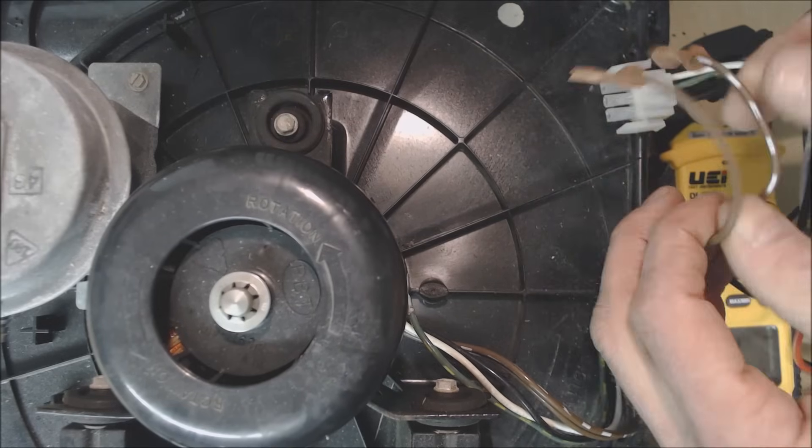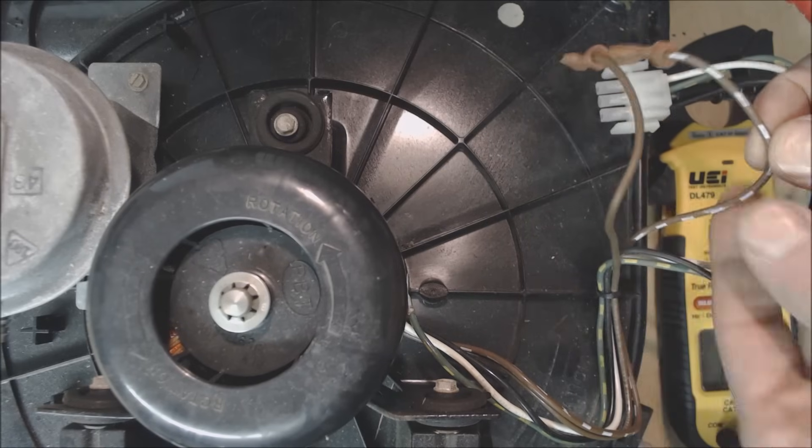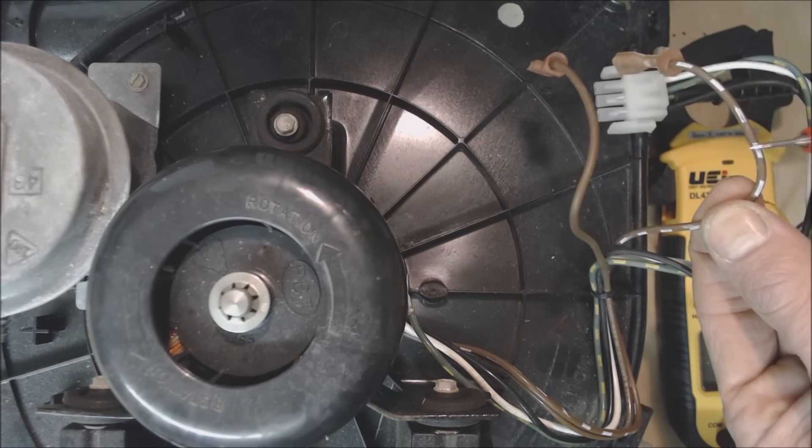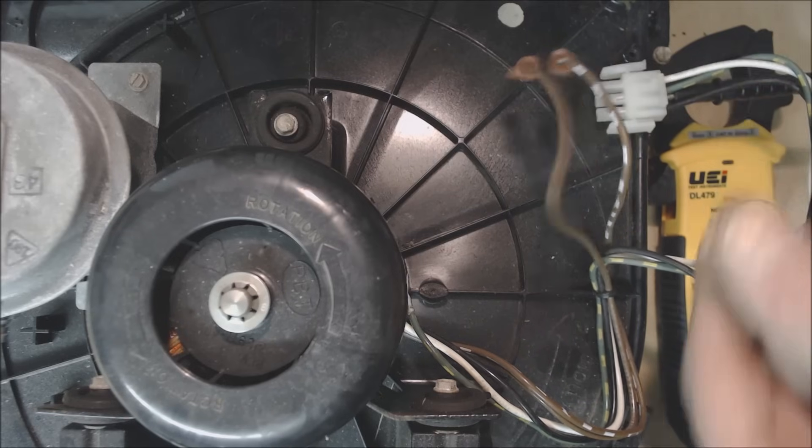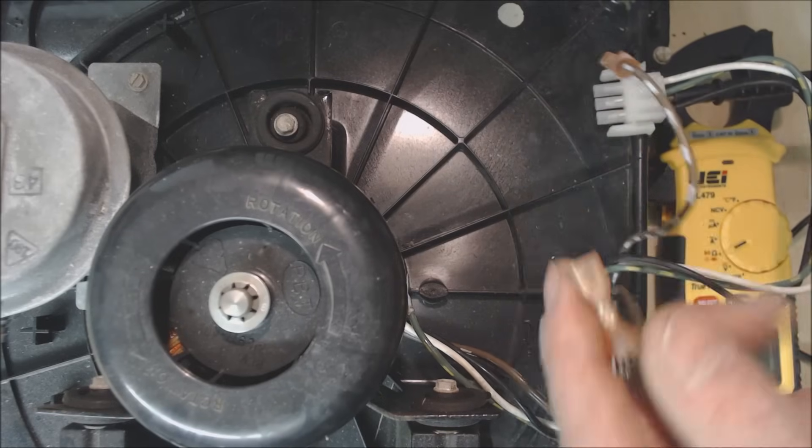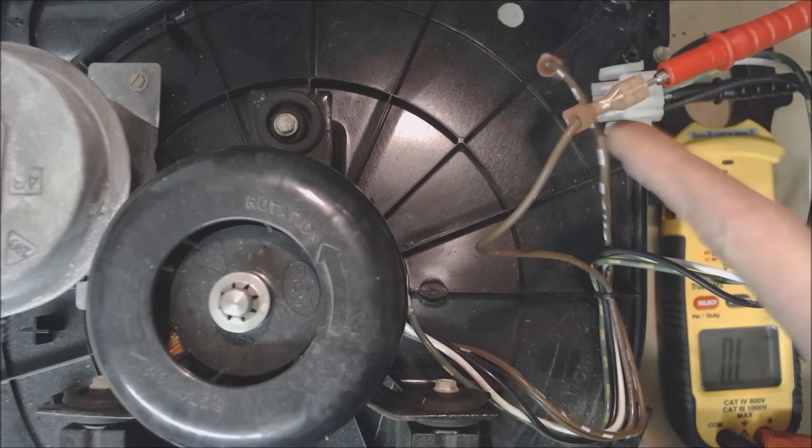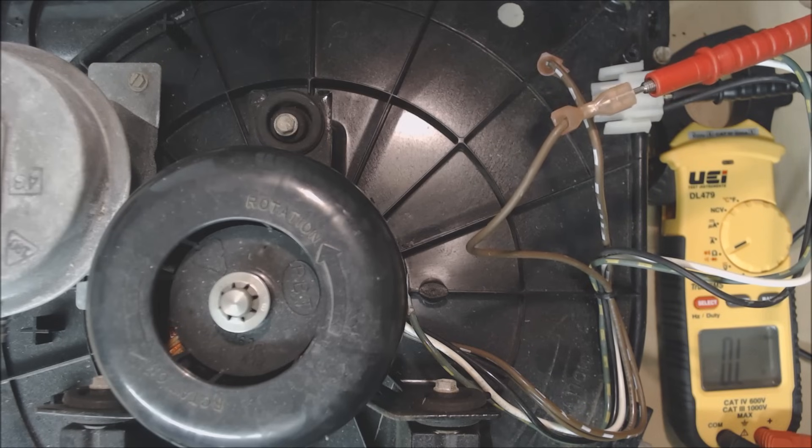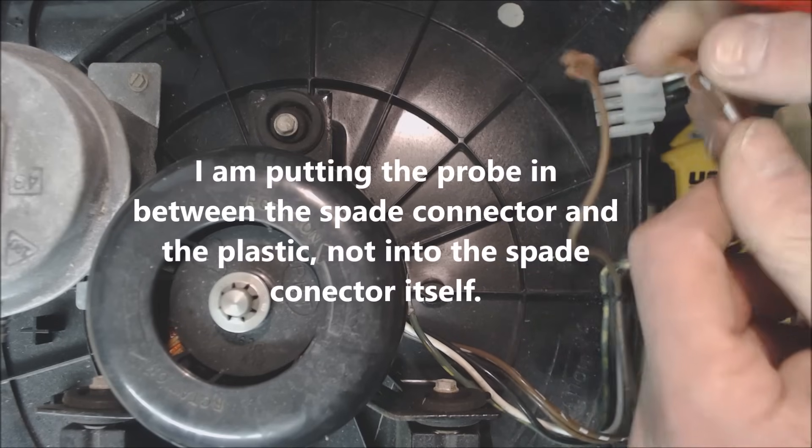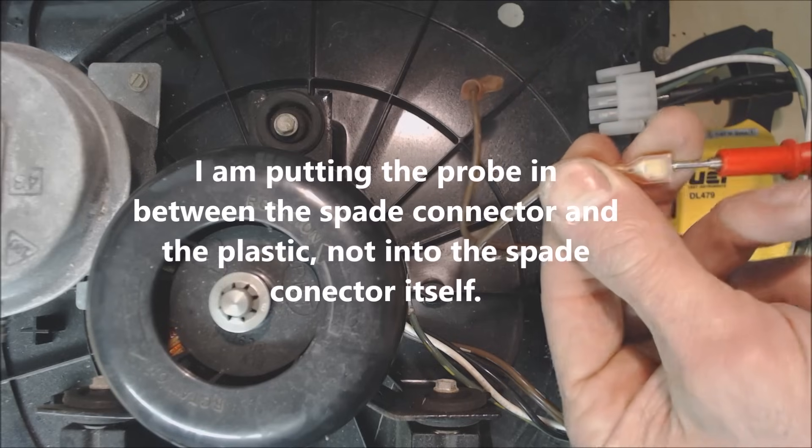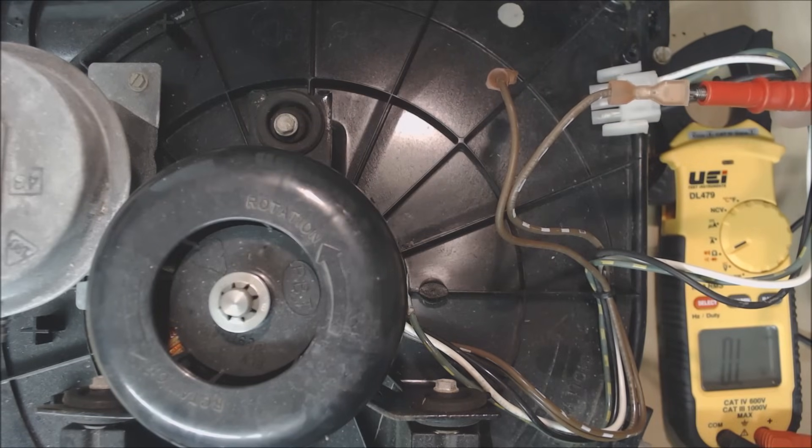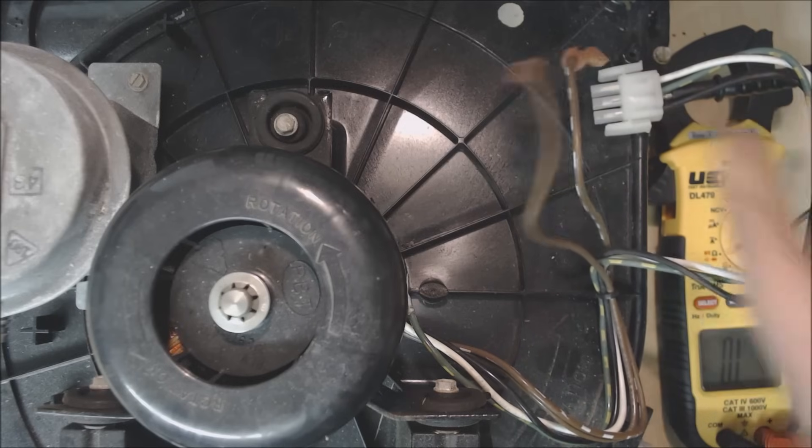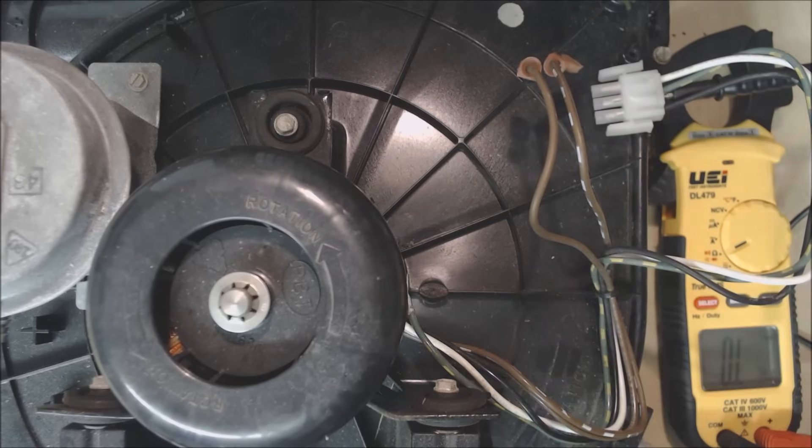And just so you know, when you have the two wires going to the capacitor, the one that's brown and white, that one's actually touching the white wire inside of this 120 volt inducer motor right here. So we already tested the white so we know that that is no problem. You see that we once again have OL and we'll check this one anyway. And you see that we have OL. So we know that the windings did not short against the ground frame. And we can see that our ground is intact. Another way to do this is actually to try to take, you know, this is all painted, but you want to take your ground connection right here at your motor.